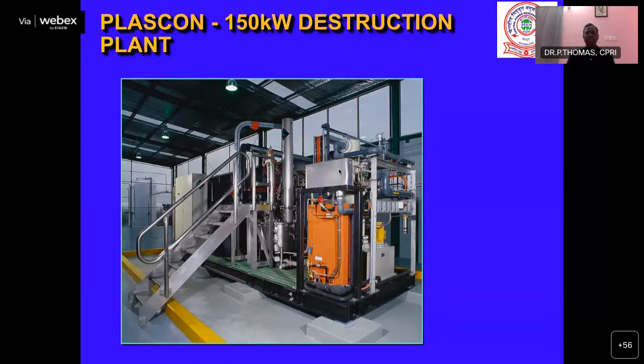And then for that contaminated oil, they have another small setup where they use sodium-based technology to treat it. So one is that you are cleaning the oil, removing the pure PCB and destroying it with this plasma technology. Then whatever contamination is inside will still be in the core, in the paper and pressboards; oil will still be there. We use some solvent. After that, the transformer is cut into 2 or 3 portions.